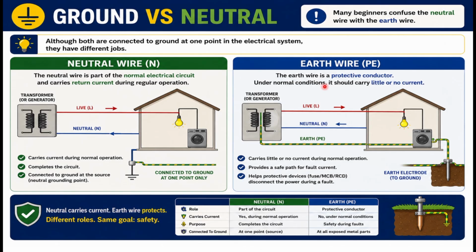Earth wire, on the other hand, is just a protective conductor. Under normal conditions, it should carry little or no current. But in case of a fault, like let's say a leakage in this washing machine, let's say we have a failed insulation, right? And we have current leaking to the outer body. That is when this earth conductor comes in. That leakage current will now flow through this earth resistance and earth conductor and go to the ground. So basically, that is the difference between the two.